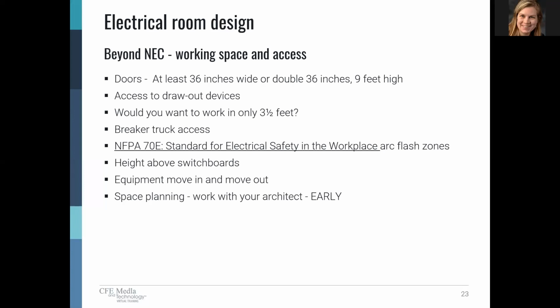The NEC does finally address doors and access doors on equipment with regards to access or egress in a room. But when you're dealing with switchgear, those are draw-out devices. We always like to look at how far those devices can draw out and add that to the overall working space. So if you might need 4 feet and the breakers draw out 24 inches, we just add that to the dimensions. Because really, do you really want to work at 3.5 feet? In many cases, that's the dimension we're using for clearance. But talk to the owner when you're designing the job, talk to the maintenance people, and if you can get more room, it's just better for everybody.